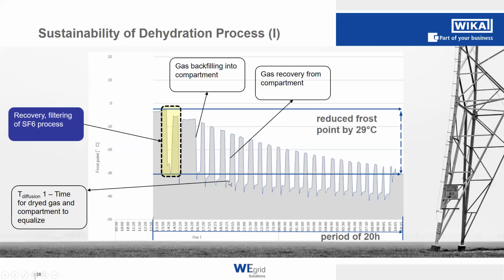Then we have a small step, for example 10 minutes, where we wait to equalize the compartment humidity from the wall into the gas again, and then we recover another portion of SF6, and the cycle starts again. Within these 20 hours, we reduce the frost point from a starting point of around -5 degrees to a frost point of -34. So the frost point temperature is reduced by 29 degrees.